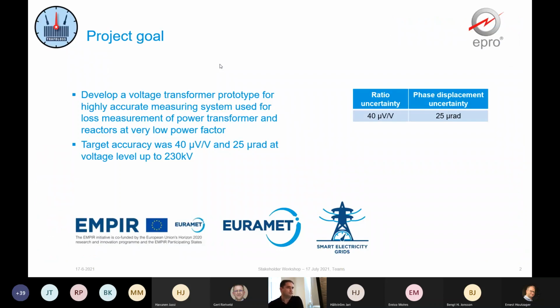Okay. The goal here, especially for EPRO, was to develop a voltage transformer prototype up to 230 kV. Regardless of the high voltage these devices have, the emphasis was on the high accuracy of the devices. As the most important part of overall measurements is the measurement of losses at the transformer, it was planned to take one part from our conventional loss measuring system, and that was the voltage transformer with its digital output. Target accuracy, as you can see, was 40 microvolt per volt and 25 microradian.